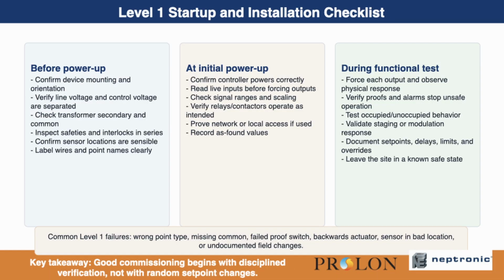A successful startup is never random. It should follow a disciplined checklist. Before power-up, the installer should verify device mounting, wiring separation, sensor placement, safeties, and labeling. At initial power-up, the team should confirm power quality, controller status, and basic input reading. After that comes functional verification, proving that each input is believable and each output produces the expected field response. The important message here is that commissioning begins with verification, not with changing set points or guessing. A structured process prevents wasted time and reduces damage risk. This mindset is especially important when working with controls, humidification, electric heat, valves, and integrated HVAC applications.